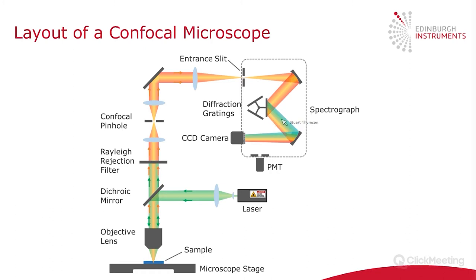The light that's been separated into its constituent wavelengths passes onto a CCD camera, which allows you to acquire the full spectrum in a single shot. For both photoluminescence and Raman steady state measurements, you would use the CCD camera. The RMS1000 can also function as a photoluminescence lifetime microscope, with a single point detector — a photomultiplier tube — to measure photoluminescence lifetimes. The light can be directed through a slit and onto the PMT for lifetime measurements.